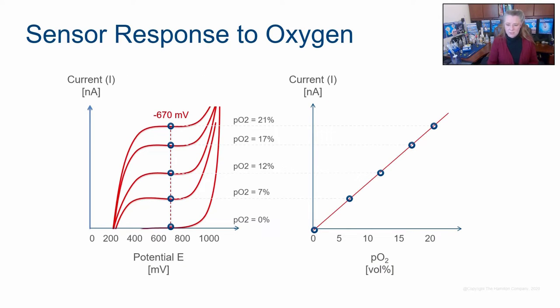And conveniently, the voltage between the anode and the cathode happens to be called a polarization potential, and it just happens that oxygen becomes fully reduced at the cathode and no other gases are affected. And since oxygen is the only gas affected, this means that the current is proportional to the partial pressure of oxygen, which is proportional to the concentration of oxygen. And you get these really cool little curves here, but it's very much a linear correlation when you look at oxygen.